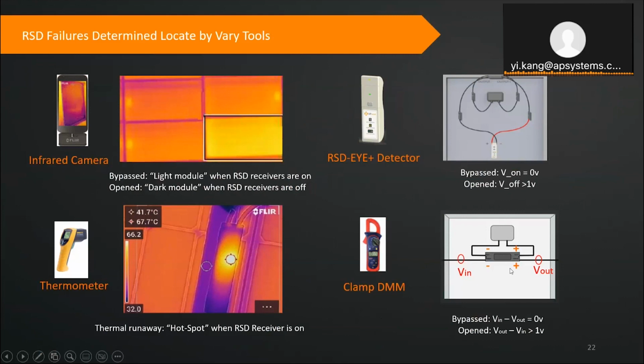That's the cheaper way. And when you get the location, you just use the DMM. Either you take it out from the string and measure its DC output to see if it's still within the safety voltage range, or you use the RSD-EYE+ to test it outside, or put it back, just to get evidence that this device has failed. So that's the last step. You can locate where the failure is.